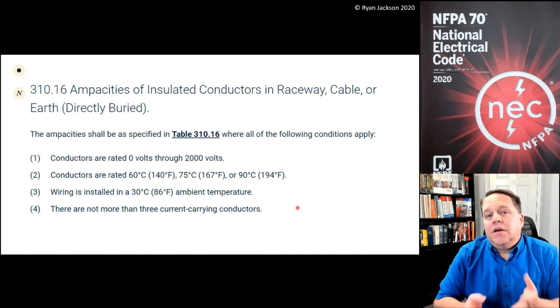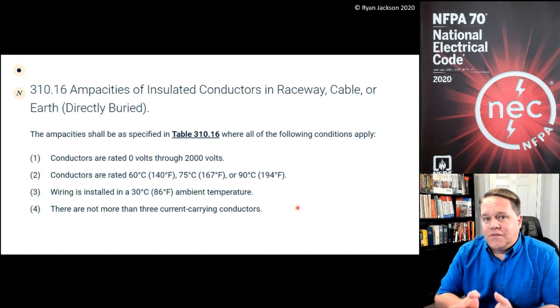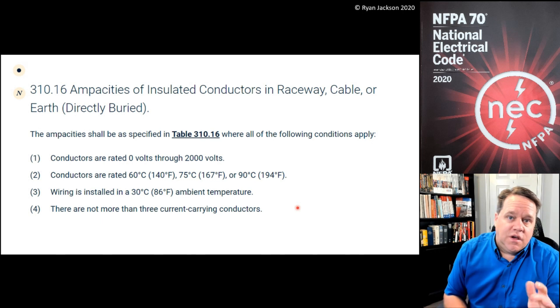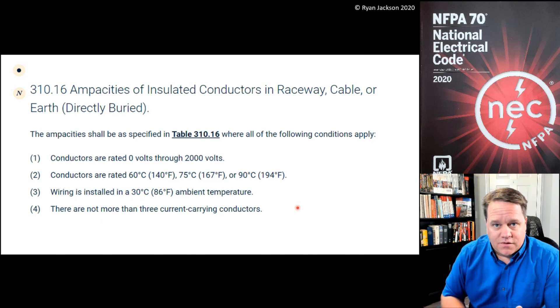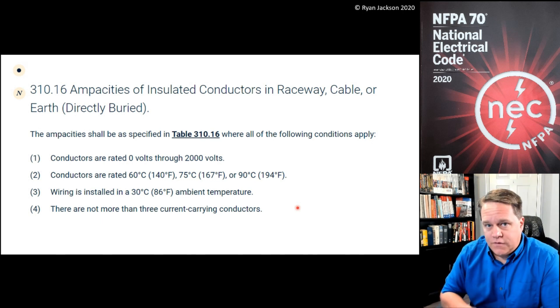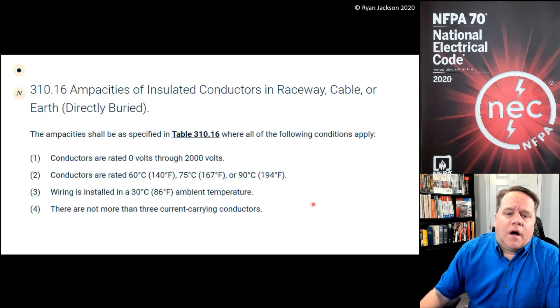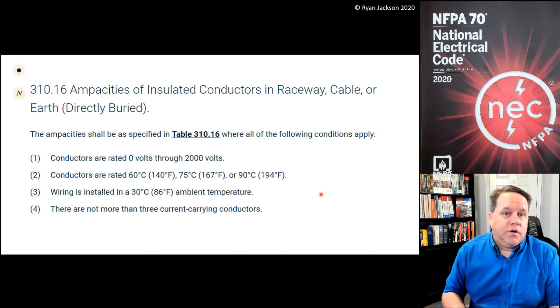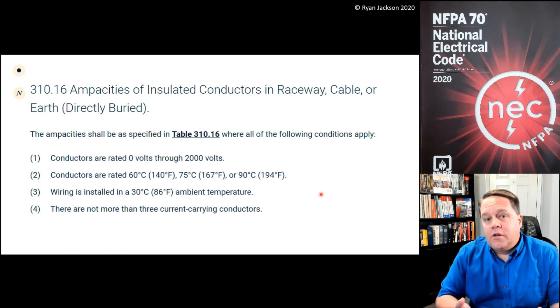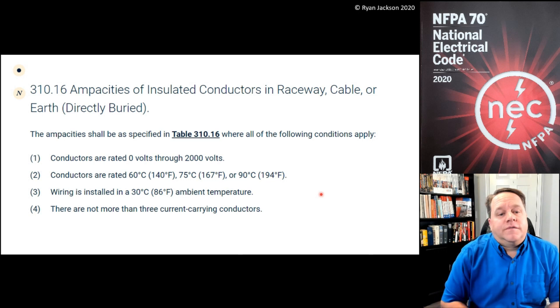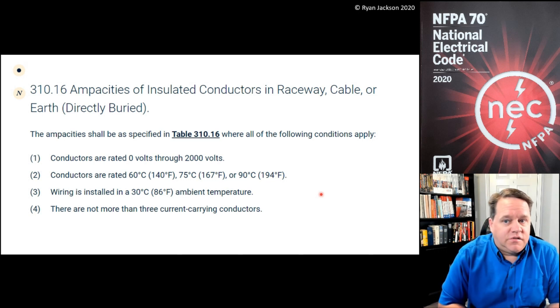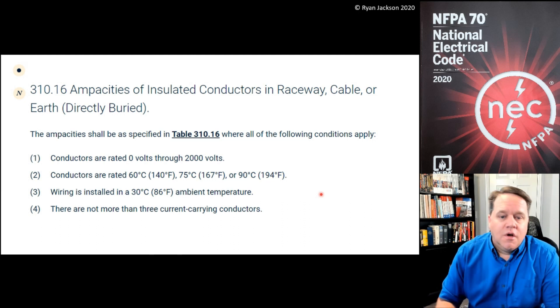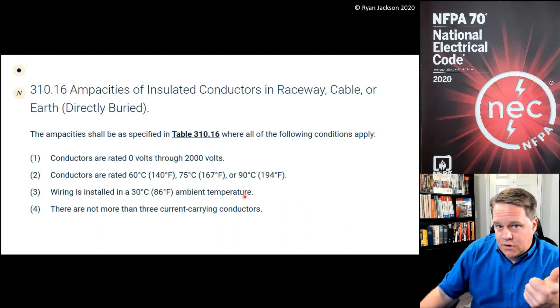If you're not in an 86°F ambient temperature, then the table ampacity in 310.16 is no longer accurate because you've changed the conditions of use. Same thing with not more than three current-carrying conductors — if you have more than three current-carrying conductors, then you no longer fall under the conditions of use specified in table 310.16, and you would have to apply an ampacity adjustment.